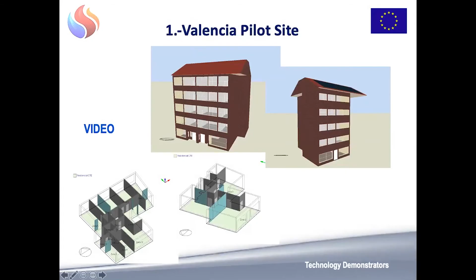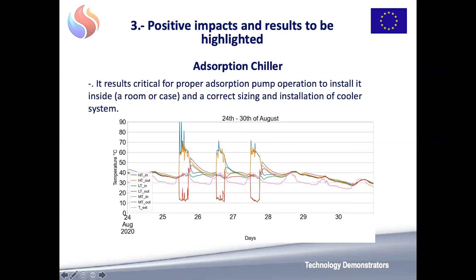I will have to say that this result is absolutely critical for the proper operation of the system - to install it inside a room or case, sizing correctly the support cooler system. What I mean is that the worst experience we had during operation of the adsorption pump was that with temperatures over 30, 32 degrees, efficiency decreases significantly. Even with temperatures over 34 degrees, cooling production was minimal. That is the reason it's so important to install it in proper conditions inside a room or case. Anyway, this equipment is not an outdoor equipment.